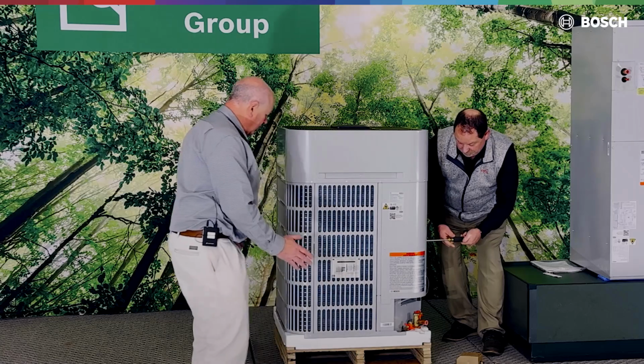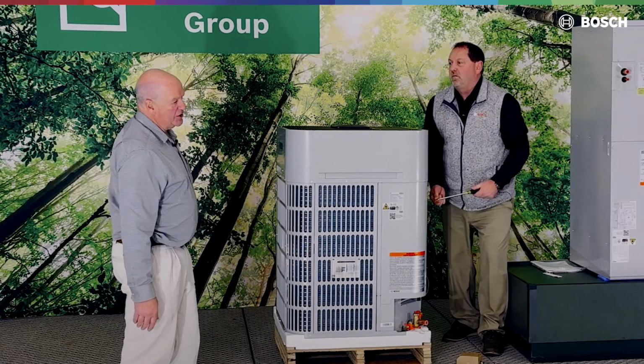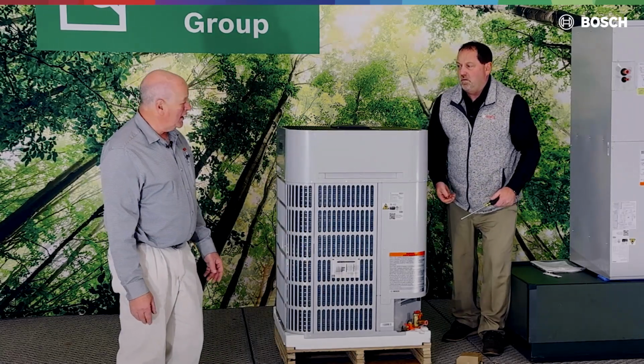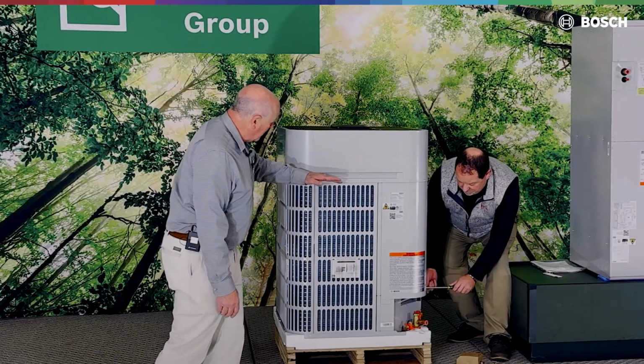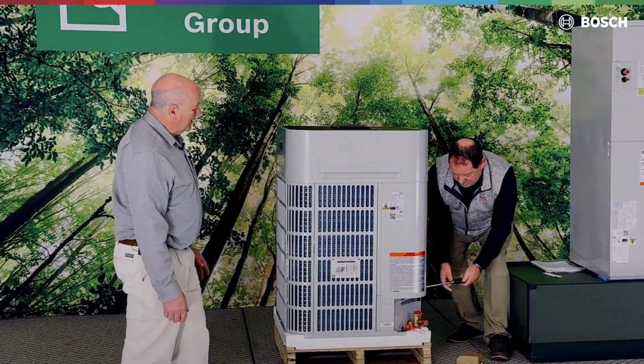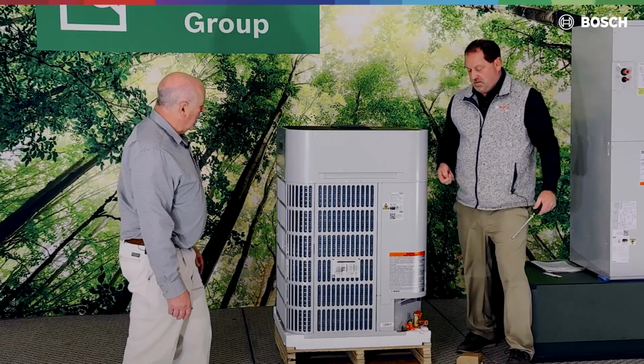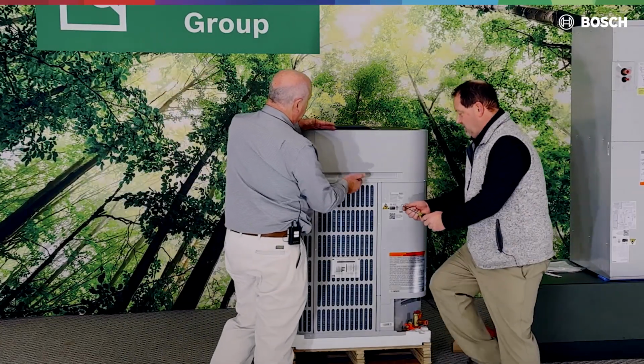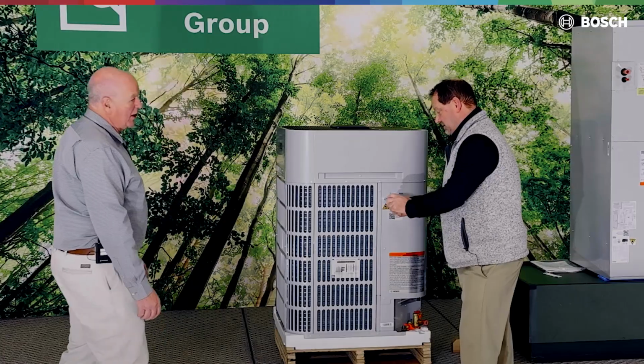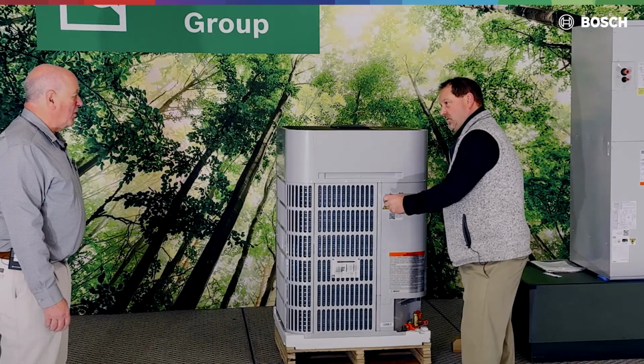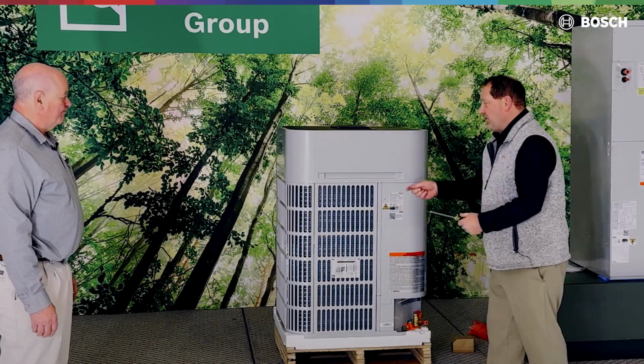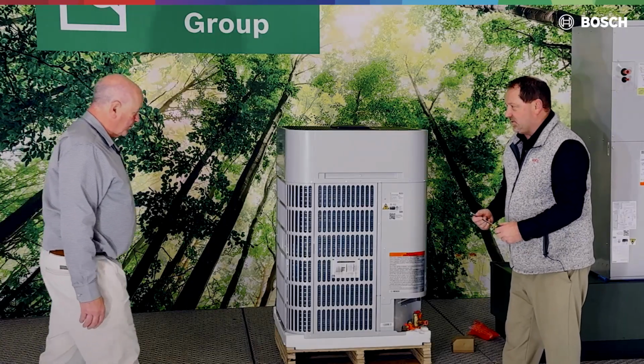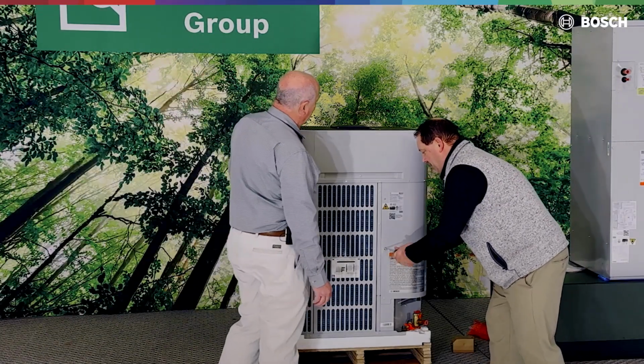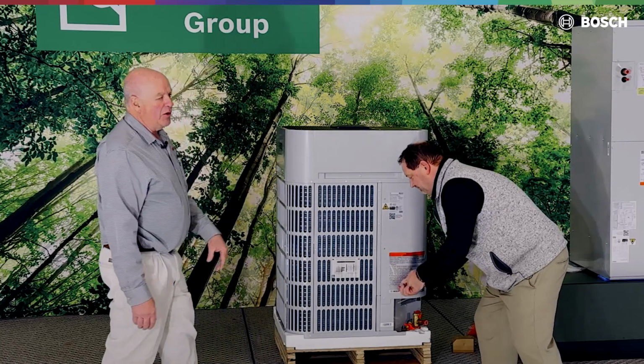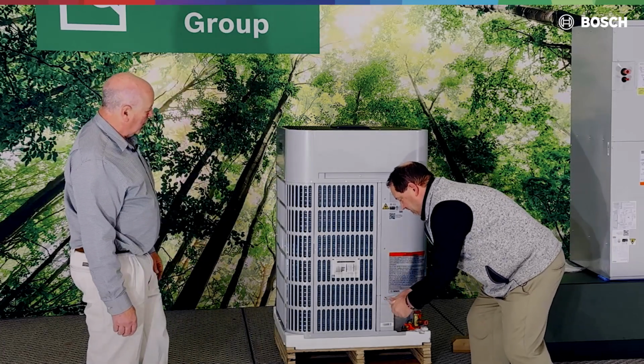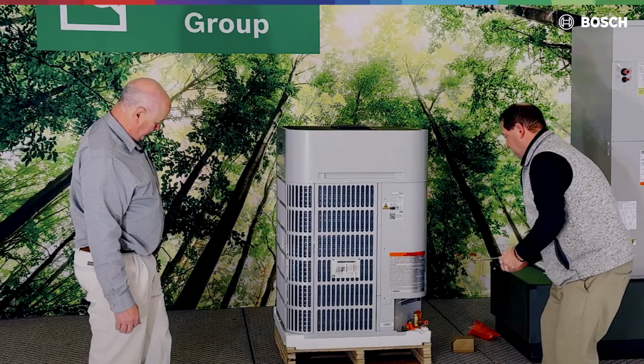Our dimensions are 29 by 29 inches. That fits through a 30 by 30 gate. That's one of the unique things with Bosch. This is a 20-SEER application unit that's relatively small. The Ultra unit has a little bit higher discharge on the fan, so this is 43 inches tall instead of the normal 33 inches on the 5-ton. So why did we need to extend this up so high? So we get more airflow, better capacity across the coil. We have some really unique features we're going to talk about as to why we would want to do that and enhance the performance of this unit.